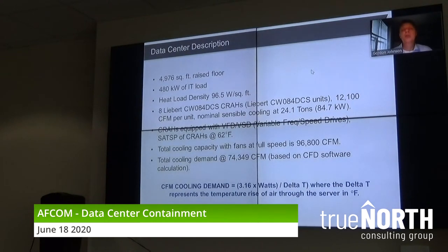But if you really want to know what your CFM cooling demand is from your IT rack, it's that formula down below in blue. It's 3.16 times your server wattage divided by the delta T, where the delta T represents the temperature rise of air through the server in Fahrenheit.